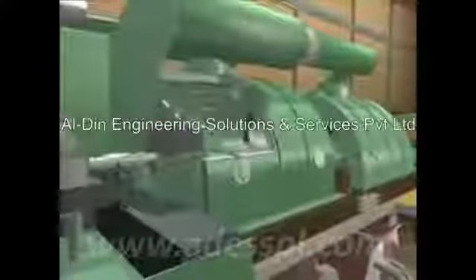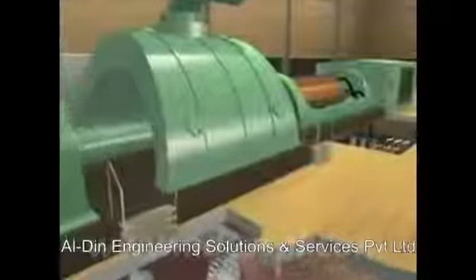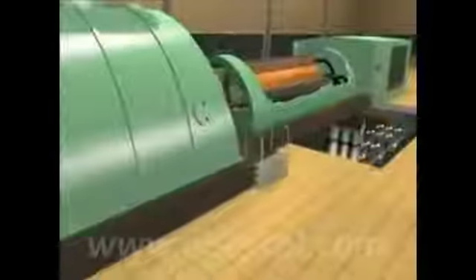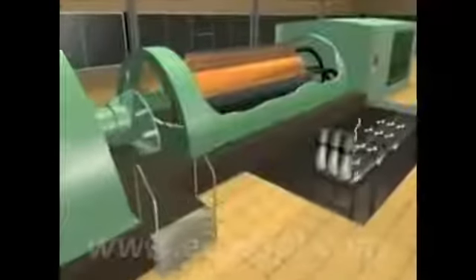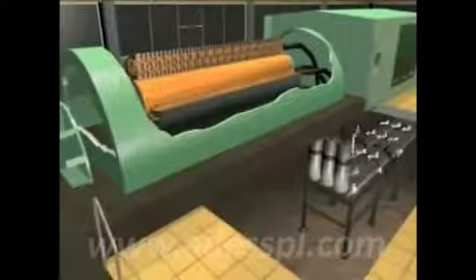Steam, now 1,000 degrees Fahrenheit at 3,500 pounds per square inch, is piped from the boiler to the first in a series of turbines. Here it expands between layers of turbine blades mounted on the turbine shaft. The steam loops back to the furnace, then onto the second turbine. In this process, the steam turns the series of turbines at 3,600 revolutions per minute, providing power to the generator, the last in the series of machines. The generator continuously creates an electrical charge of 34,481 amps at 18,000 volts of electricity. From here, the electricity leaves the plant and begins its journey to customers.